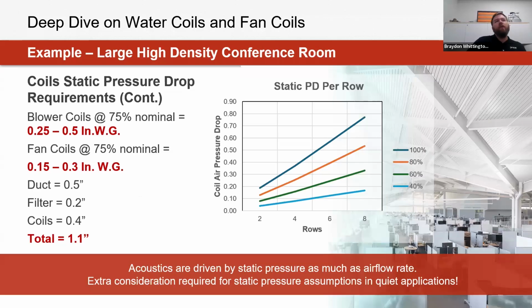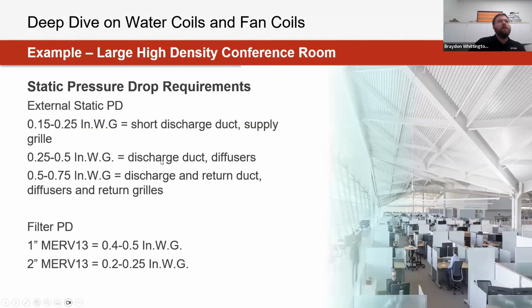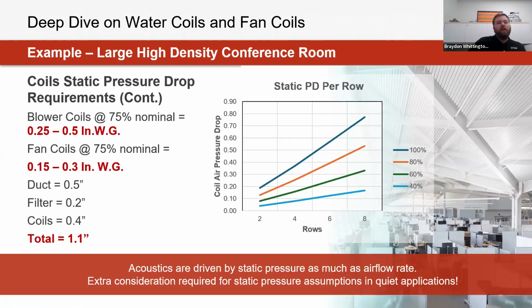And when we're talking about pressure drop, we also need to take into account, and can't forget about, our part one about water coils, as they're also having some form of pressure drop that is adding onto our system as well. So when selecting around that 75% nominal range for these units, we're starting to see around quarter-inch to half-inch of pressure for blower coils at that nominal range. And this is just average, just for any of you that might be trying to calculate this, or just for a reference point, or fan coils around 0.3 inches. And with that, we can add all these together based off of our duct configuration, and we're just assuming our second configuration for discharge duct and diffusers here, filtration, as well as the coil pressure drop, for a total pressure of 1.1 inches of external static that we need to take into account.